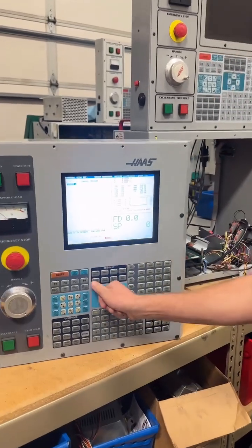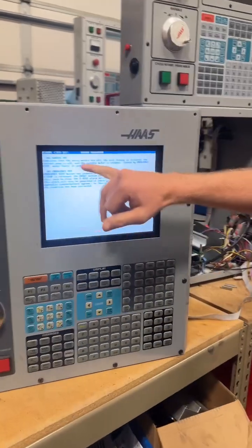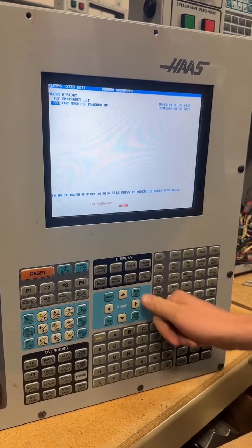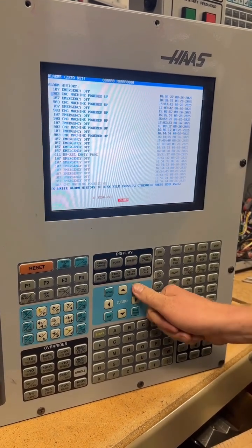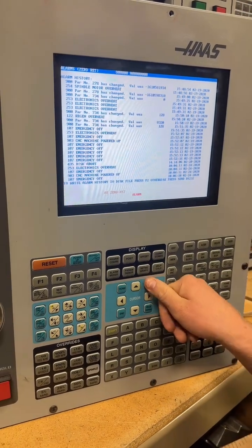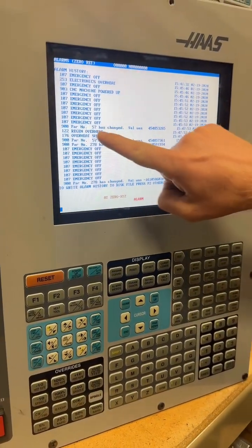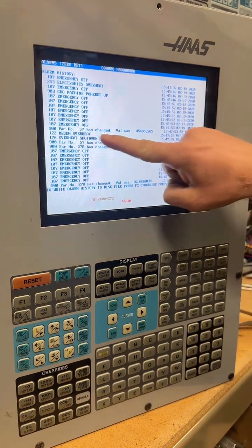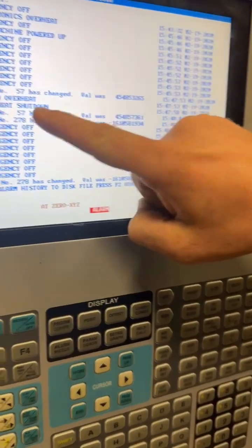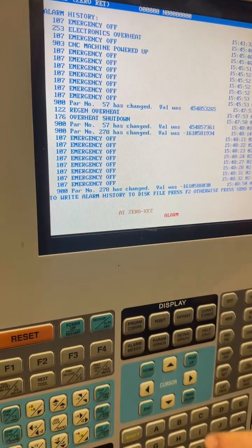On this machine, we're going to press the alarms page. Here are the active alarms. But if I press the right arrow key, I can see the alarm history. Now if I press page up, we can keep going and see more. Here is a parameter that's changed on this date and time, and here's an overheat shutdown alarm.